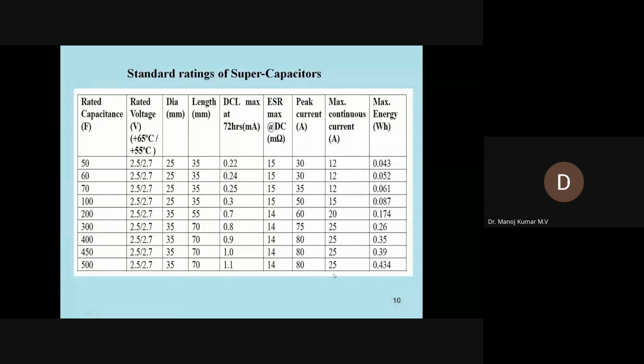Additionally, the continuous current it can supply is 25 ampere. The term I mentioned earlier is called DCL, given in one column, which stands for DC leakage, typically on the order of microampere or milliampere. For a 500 farad capacitor, it is on the order of 1.1 milliampere.